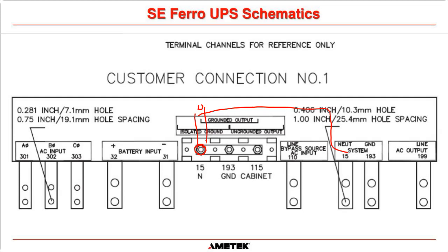Okay. This terminal here, let me clear that out. This terminal here is connected to this ground terminal. Okay. And then this terminal is connected to the chassis of the UPS itself. So the metalwork inside the UPS is connected to that terminal there. So if you want to run an ungrounded output, in other words, which is going to be in most cases the way that you do that, you do want your ground to be connected to the cabinet. Okay, you want that as a bonding point.